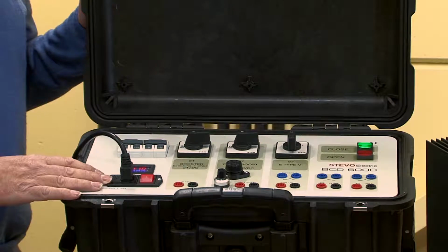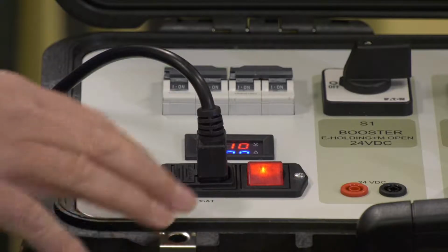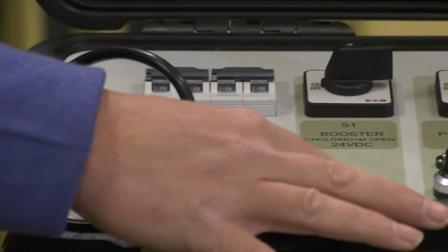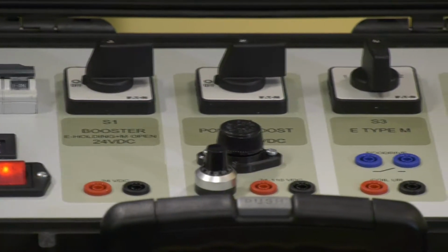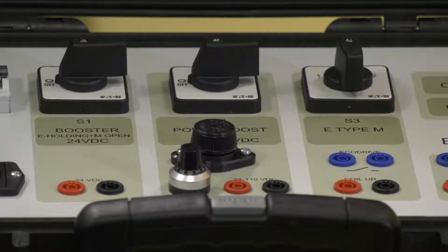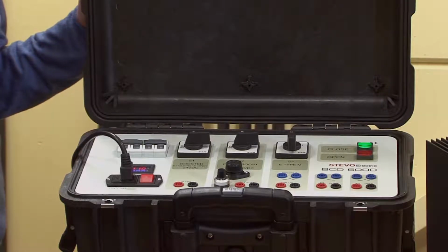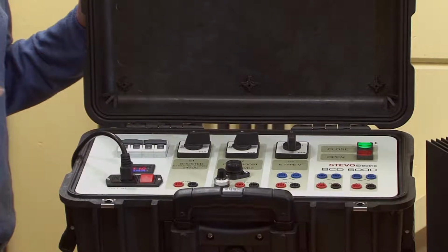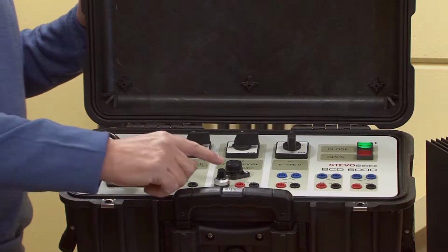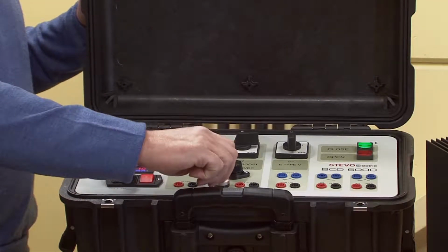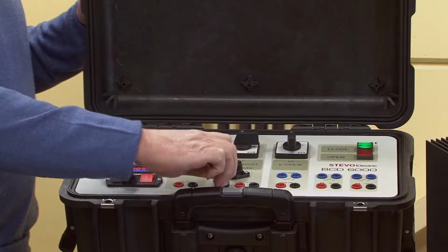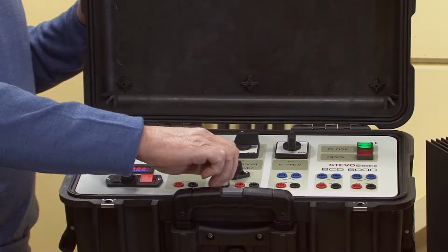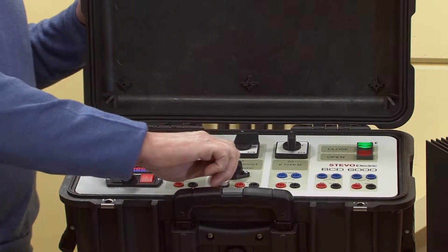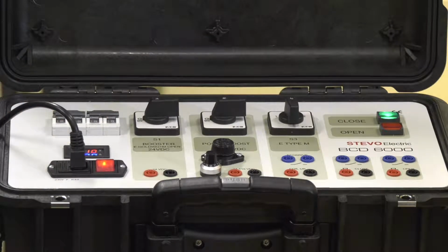It contains two power supply units, a power supply of 24 volts and an adjustable power supply which ranges between 24 and 110 volts DC. This is easily adjustable by turning this knob. As you can see, it's now at 100 volts and it's adjusted to 110 this time.